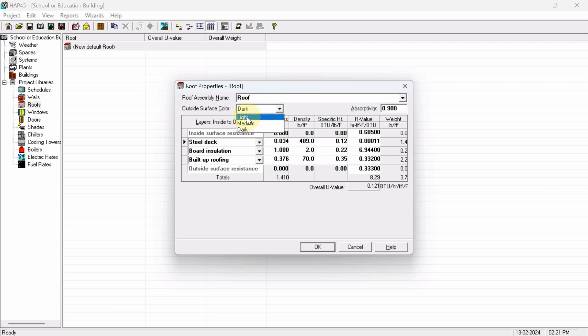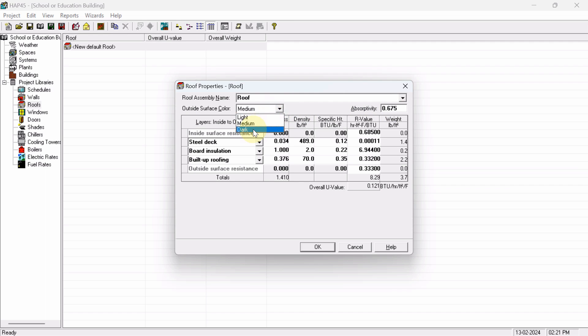From the list, I have already discussed that light color will absorb 45% of heat, medium color will absorb 67%, and when you are selecting dark color, it will absorb 90%. So always we have to select the dark outside surface color, because we always have to design for peak condition.